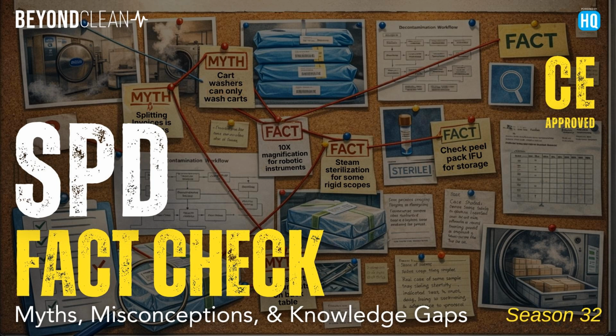That back and forth is always interesting when the market really wants something, like these big flexible endoscopes, large diameter flexible endoscopes—everybody wants those scopes to be sterilized. But what's going to move first? Regulatory has to move, the manufacturer has to design something that can handle the sterilization, and the sterilizer company has to innovate cycles that can handle the long lumens and the weight of the thing. So there are lots of pieces that need to move in that direction as we talk about innovation going forward.